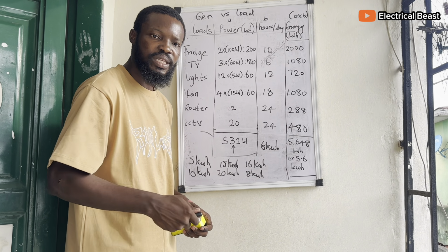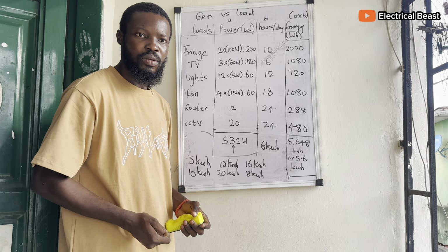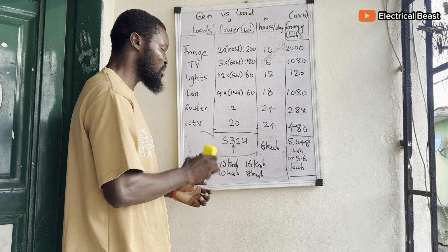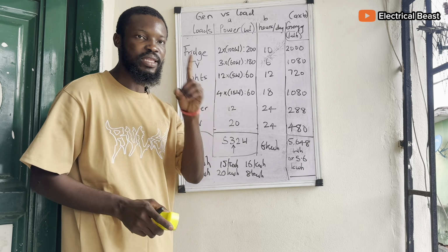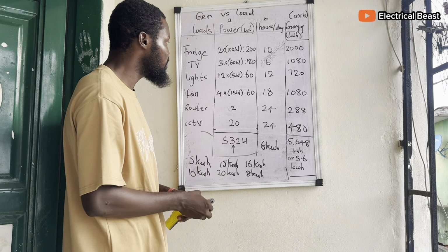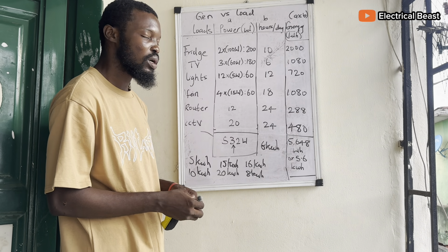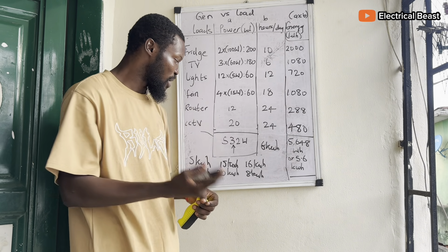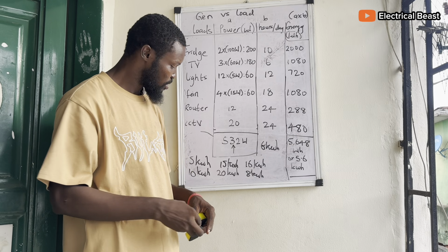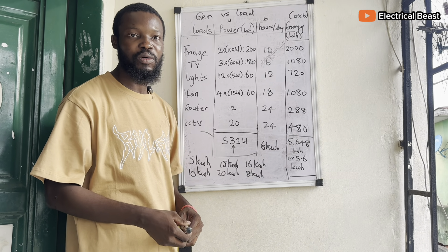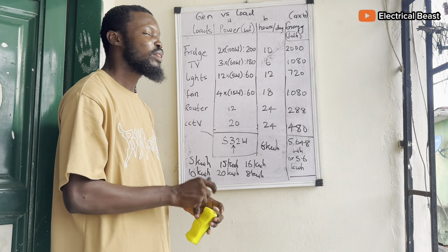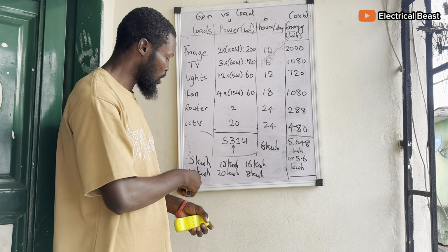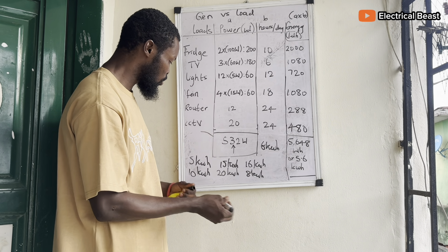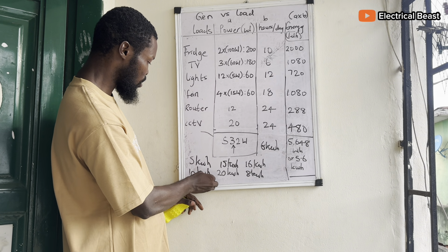Now, what's the backup days? Backup days differ. If you want this system to be able to power all these loads for one day, multiply this 10 kilowatt by 1. That will give you 10 kilowatt hour. But if you want to be able to power these loads for 2 days, multiply 10 kilowatt hour by 2. That will give you 20 kilowatt hour. So let's make things simple. I want one day. So let's see, we have 10 kilowatt hour.